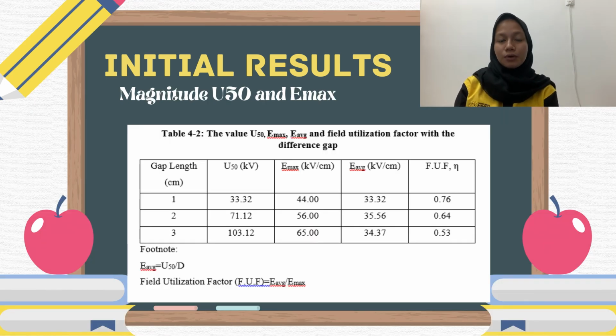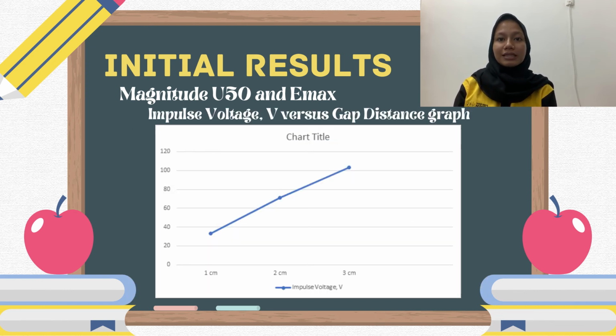The table below shows the analysis results: the experimental U50, the Emax value from the simulation using FEMM software, the Emax average, and the field utilization factor, FUF, for the sphere-to-sphere electrode configuration with gap distances from 1 cm to 3 cm. From the graph below, the impulse voltage V versus gap distance shows that as the gap distance increases, breakdown becomes more difficult, and a higher impulse voltage is required to break down the air. This is because the electrons are unable to restore their energy, so they collide with each other, resulting in an electron avalanche across the gap and a breakdown.